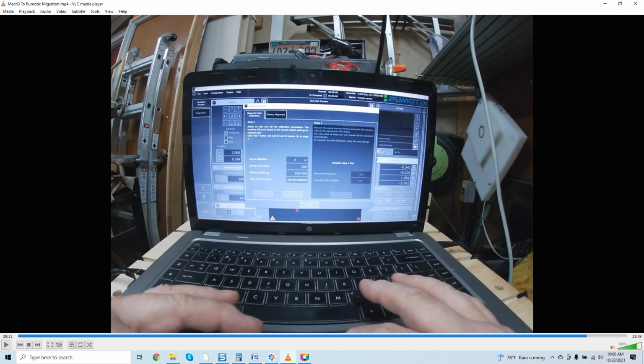over and over again, readjusted in motor tuning until you find the sweet spot, the operational envelope, so to speak, before we miss steps or we lose accuracy and then we back off. Well, when we designed the actual calibration module, the guys made it so that the software arbitrarily sets a default speed, but you, the end user, can manipulate this speed over and over again independently. So as you're calibrating, you're actually killing two birds with one stone, because you're then calibrating to this particular speed.